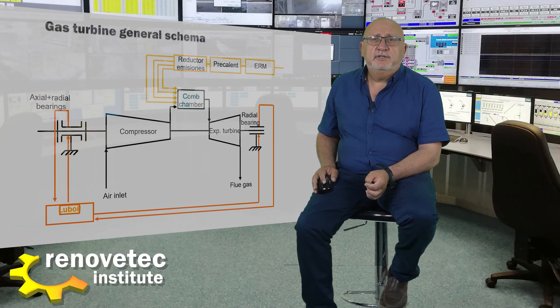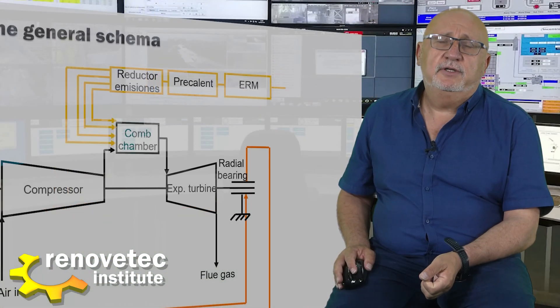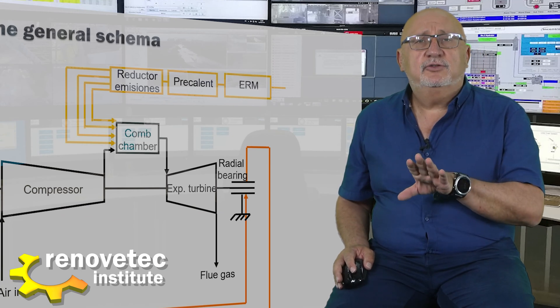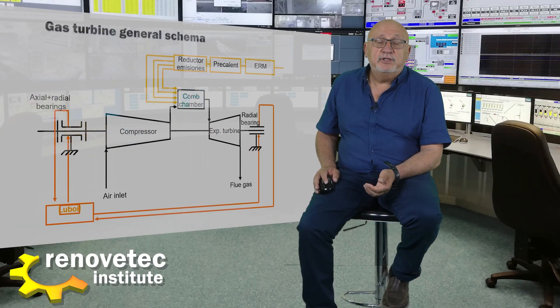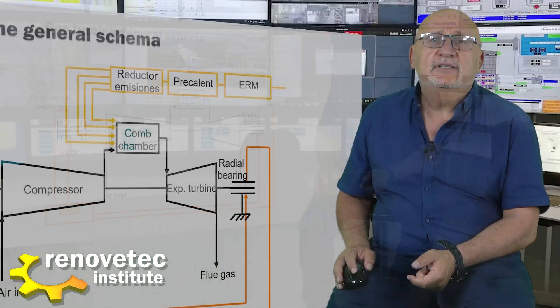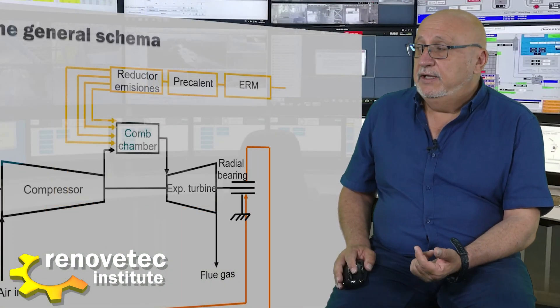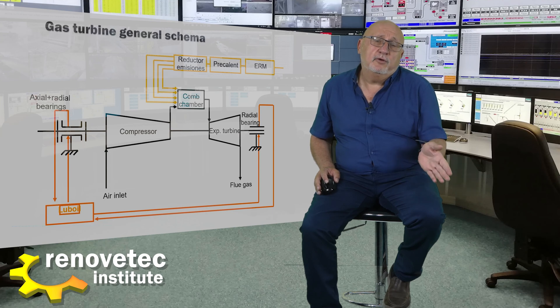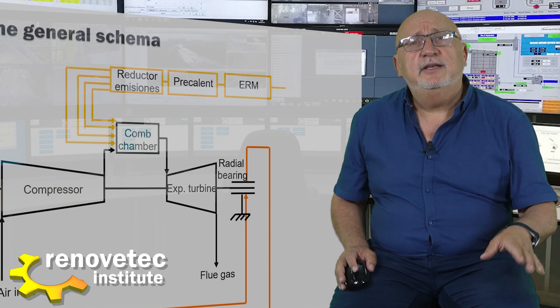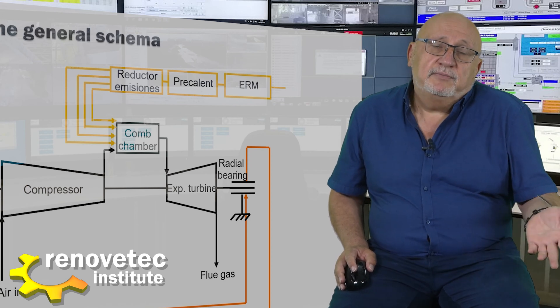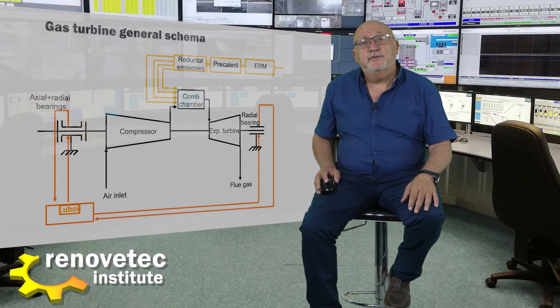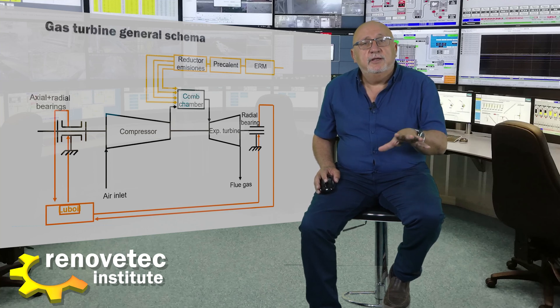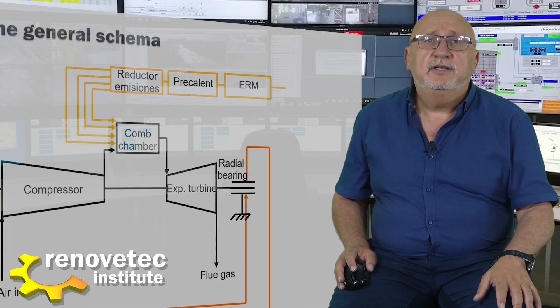The combustion chamber needs several auxiliary elements. First, we need a gas station that supplies the gas required for the turbine. Second, sometimes we need to preheat the gas to avoid it entering the turbine too cold. And sometimes, depending on the technology of the turbine or the fuel being used, we need a NOx reduction system — sometimes using water or steam, or a dedicated burner technology system to reduce NOx emissions.